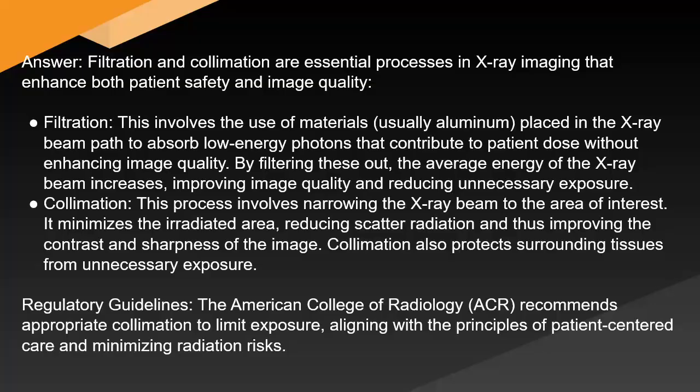Filtration: this involves the use of materials, usually aluminum, placed in the X-ray beam path to absorb low-energy photons that contribute to patient dose without enhancing image quality. By filtering these out, the average energy of the X-ray beam increases, improving image quality and reducing unnecessary exposure.